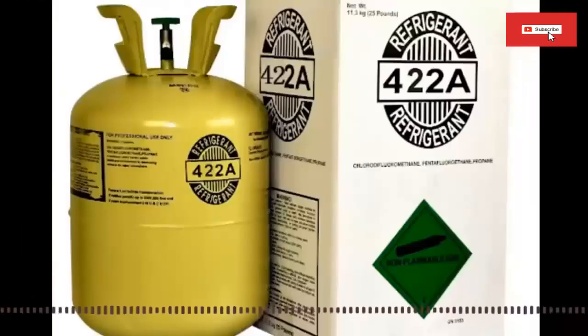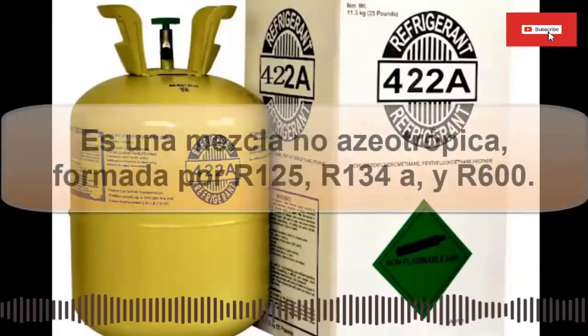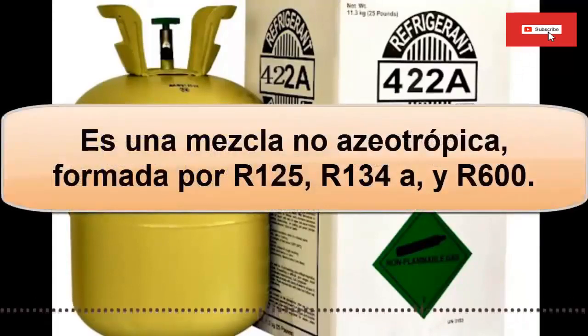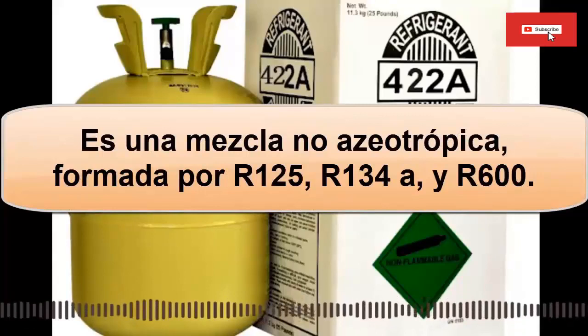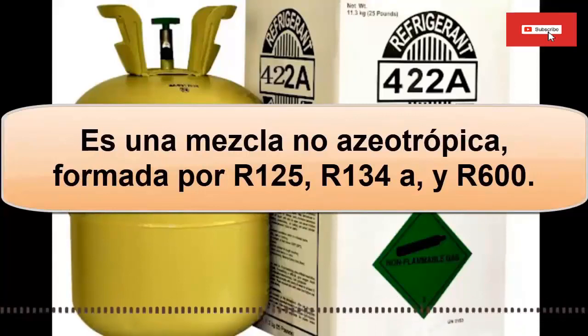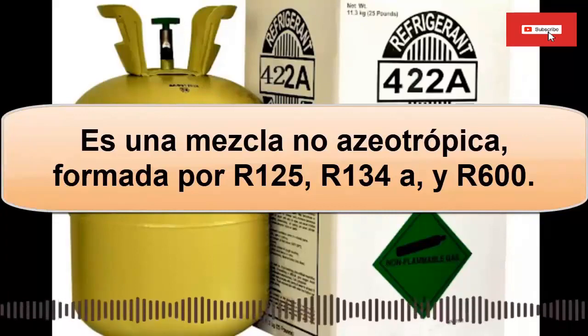In this video, we are going to talk about R422A refrigerant. Let's start by saying that R422A refrigerant is a non-azeotropic mixture, made up of R125, R134a and R600a (isobutane), which constitutes one of the alternatives used to replace HCFC hydrochlorofluorocarbon mixtures with no effects on the ozone layer.